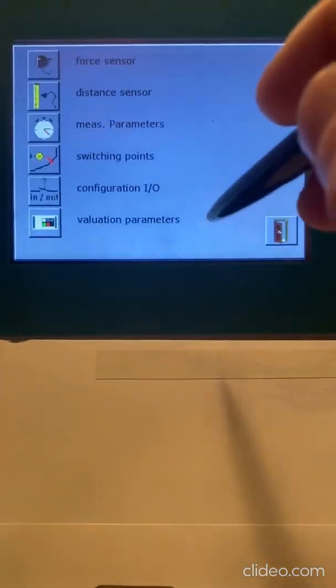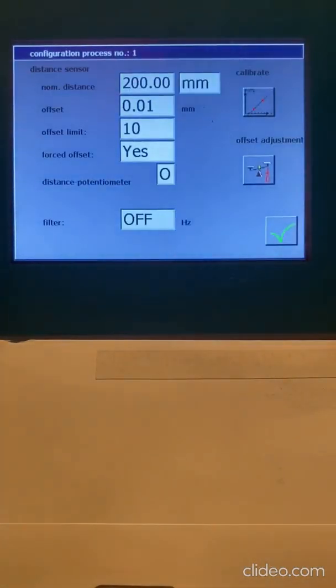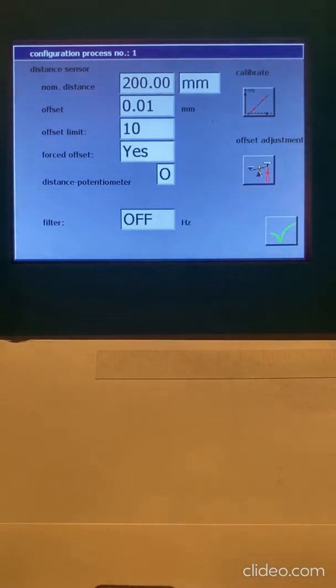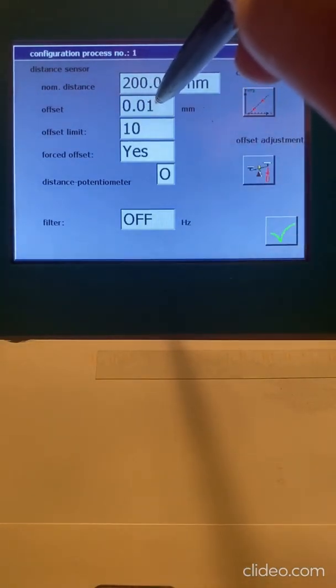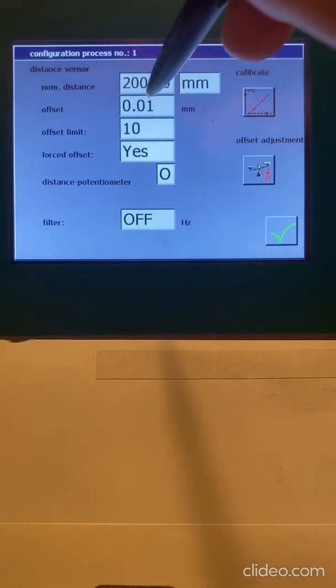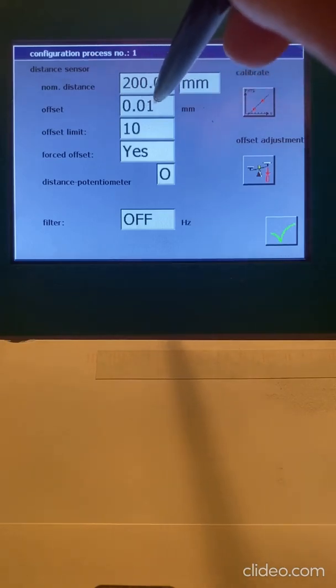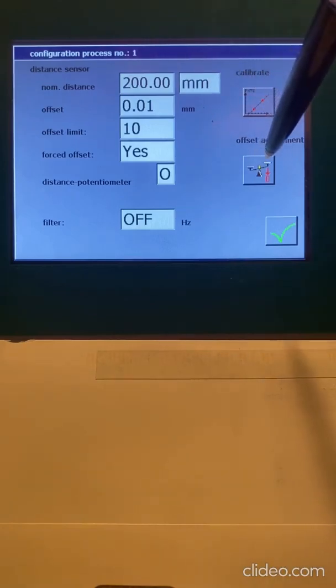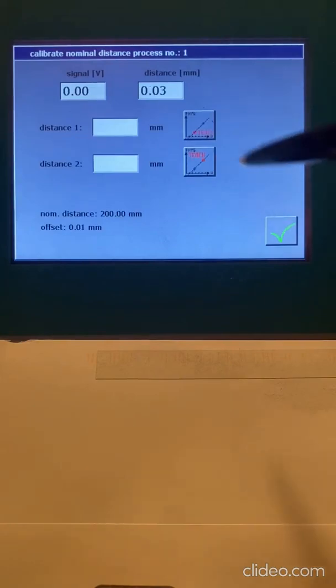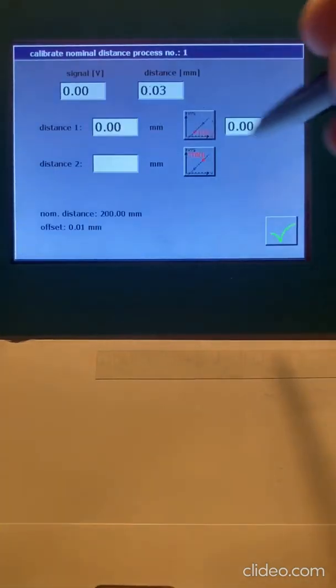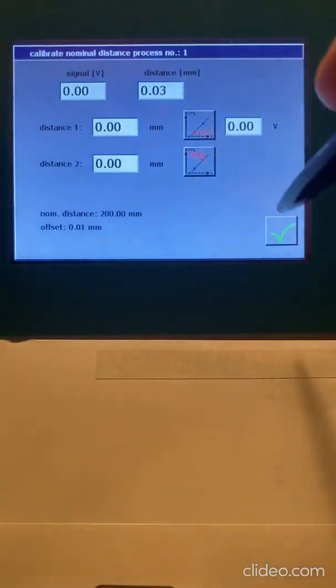I can also, I'm going to save this for this process, I can also go to my distance sensor and do the same thing. It's a 200-millimeter total stroke. My offset limit is 10, which means that zero happens at this small piece. Here's my offset adjustment, which is a zero, and I can do a two-point calibration. Same thing.